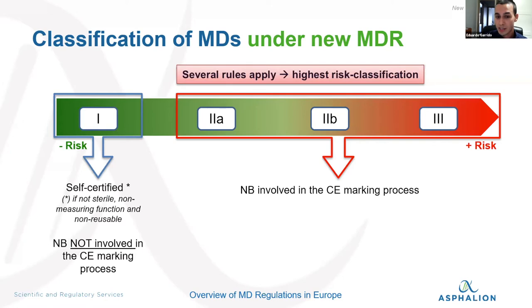On the other hand, if your device is class 2A, class 2B, or class 3, you require the involvement of a notified body. That means somebody else, an entity, is going to be assessing that your device complies with the regulation.